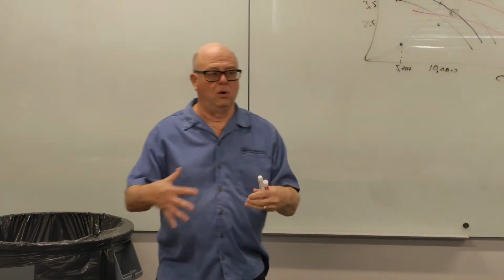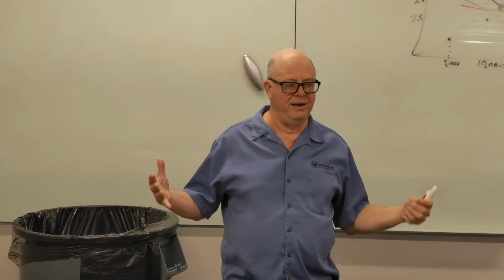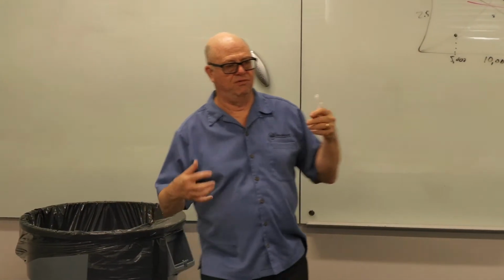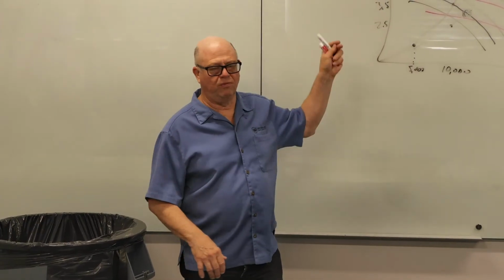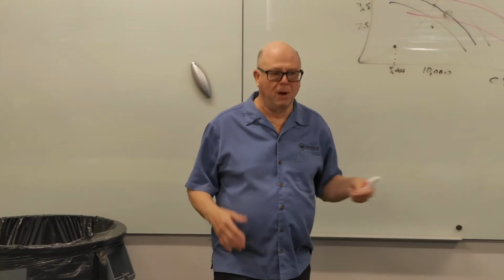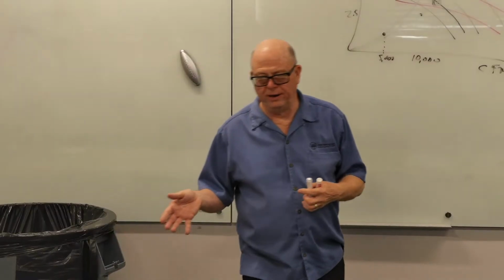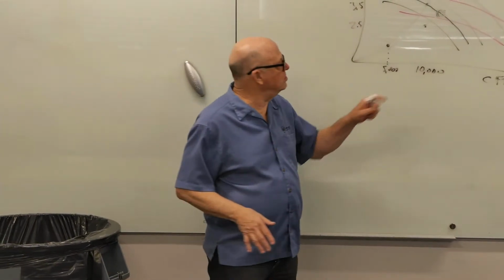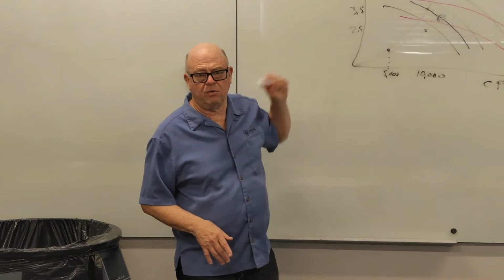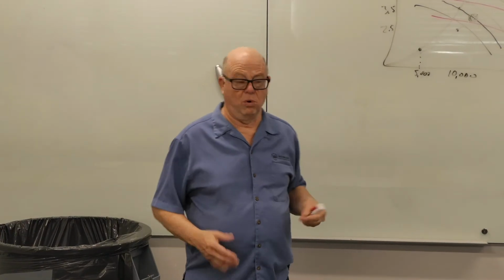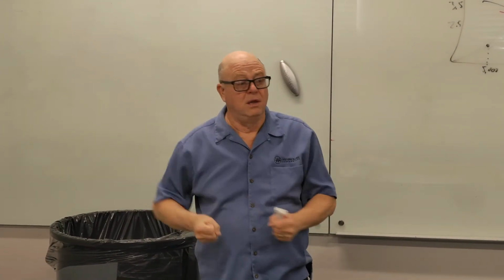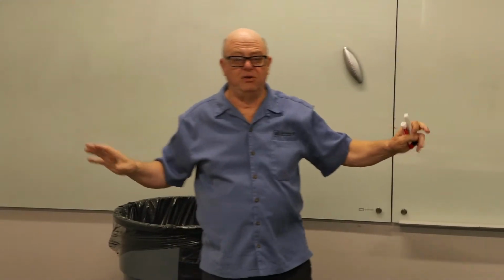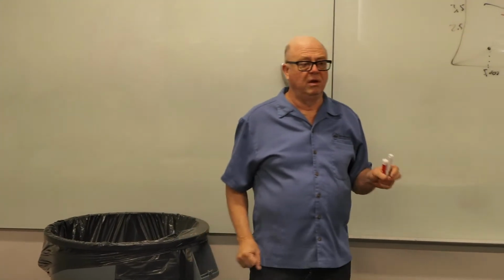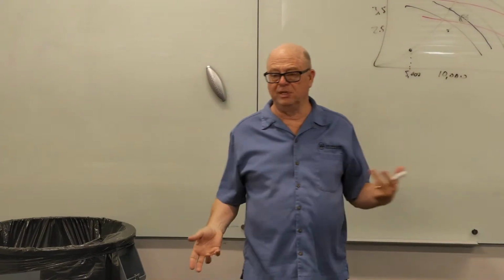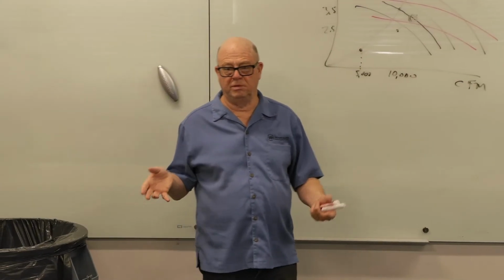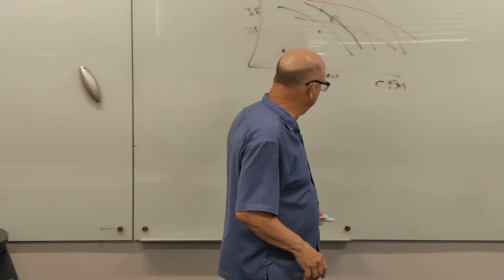And airflow is like 2 to 3 times more in terms of power usage as opposed to overcoming the static. Pumps work pretty much the same way. So there's wisdom in trying to get the static right, or if it's a pump, the head right. If you grossly overestimate and you're not on a variable speed drive, you're going to have some massive pulley changes to do at startup to get the thing to work correctly.